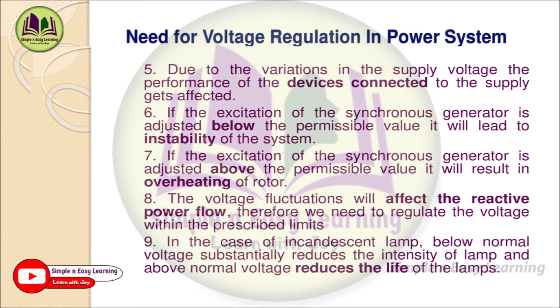Sixth, if the excitation of the synchronous generator is adjusted below the permissible value, it will lead to system instability. Constant excitation must be given to the synchronous generator to get a constant voltage output. If excitation goes below the permissible value there will be oscillations. Seventh, if excitation is adjusted above the permissible limit, it results in overheating — the field current increases beyond the limit, causing the field winding to heat up and potentially burn.